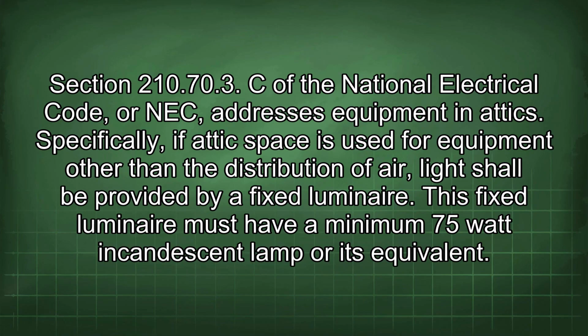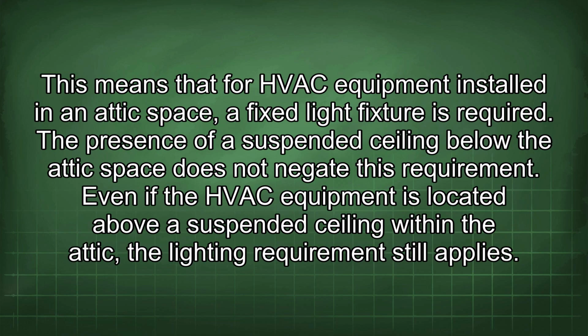210.70.3.C of the National Electrical Code, or NEC, addresses equipment in attics. Specifically, if attic space is used for equipment other than the distribution of air, light shall be provided by a fixed luminaire. This fixed luminaire must have a minimum 75-watt incandescent lamp or its equivalent. This means that for HVAC equipment installed in an attic space, a fixed light fixture is required.